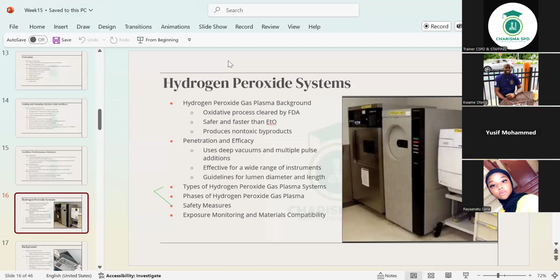So all you do is put the cassette in there, and when it's out of cassette, it's going to tell you. So you put the cassette in, you prepare the instrument, put it in with the necessary BIs and chemical indicators, and then select the cycle that you want. It goes on working. It's not even as crazy or detailed as getting exposed to the gases. It's not easy to get exposed to the gases. They are engineered in a way that is very safe to operate in. Even though I keep cautioning you that your safety is in your hands, it's still very, very safe to stay and to use it.